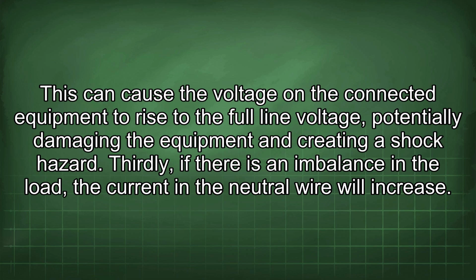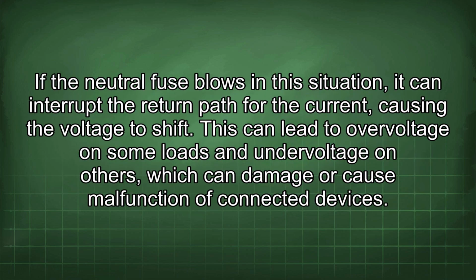Thirdly, if there is an imbalance in the load, the current in the neutral wire will increase. If the neutral fuse blows in this situation, it can interrupt the return path for the current, causing the voltage to shift.